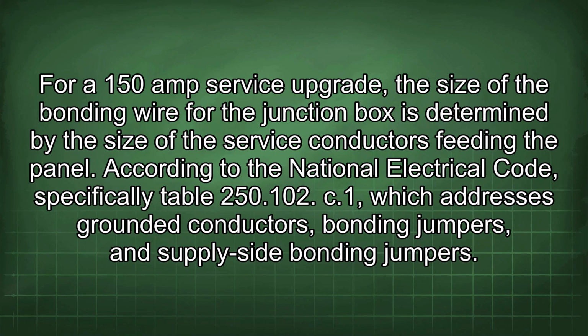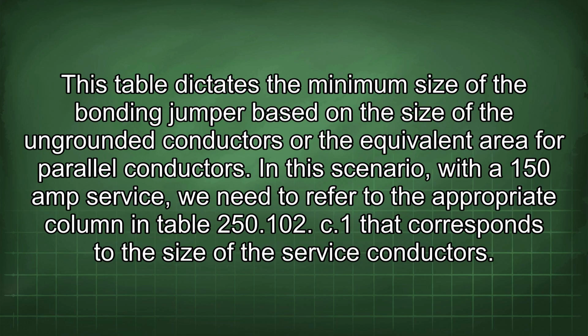For a 150 amp service upgrade, the size of the bonding wire for the junction box is determined by the size of the service conductors feeding the panel. According to the National Electrical Code, specifically Table 250.102(C)(1), which addresses grounded conductors, bonding jumpers, and supply-side bonding jumpers. This table dictates the minimum size of the bonding jumper based on the size of the ungrounded conductors or the equivalent area for parallel conductors.